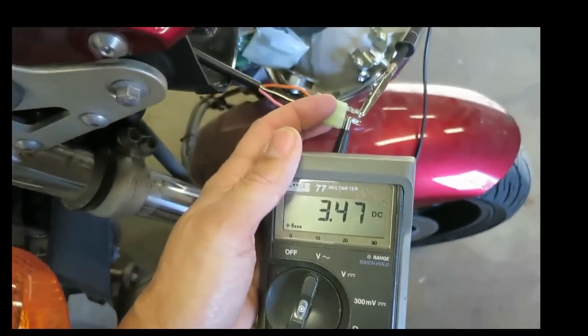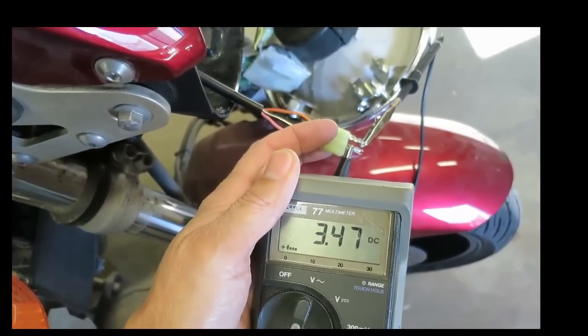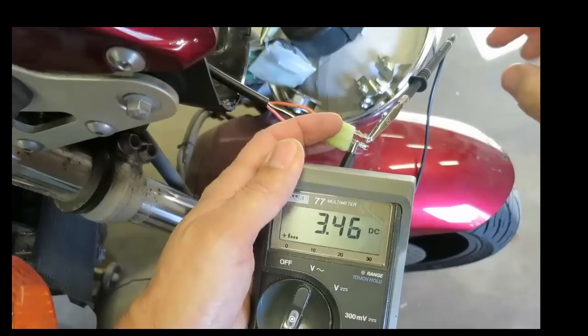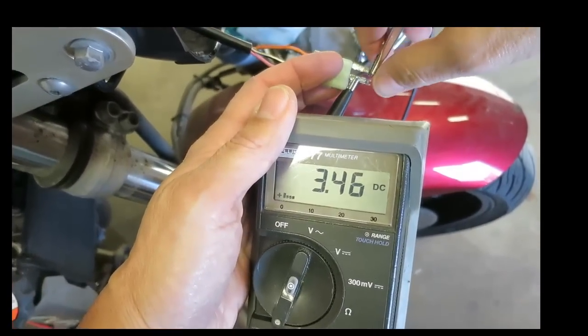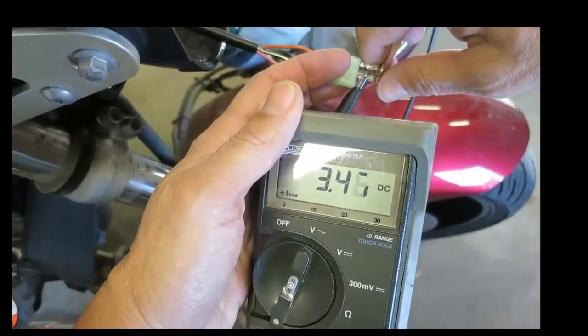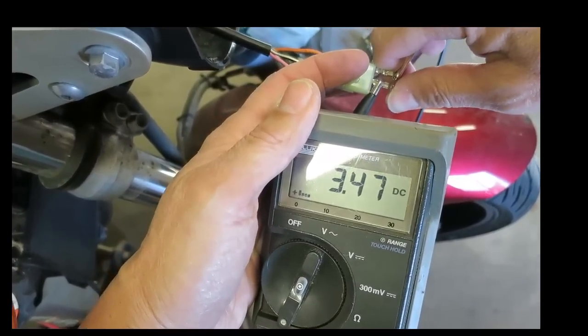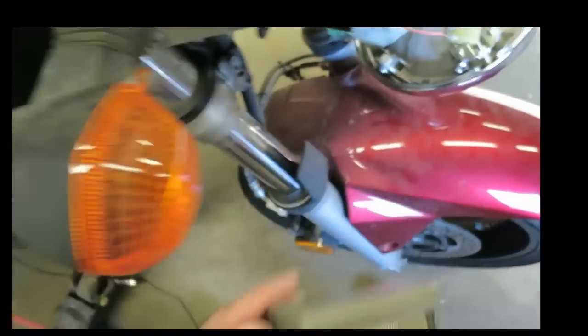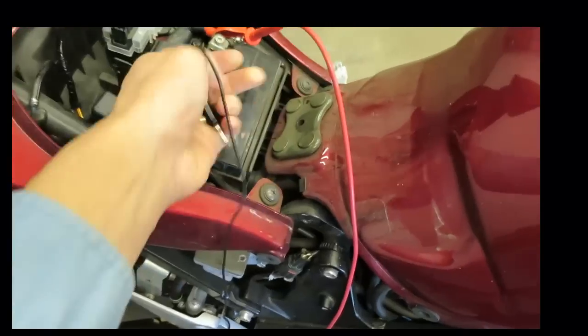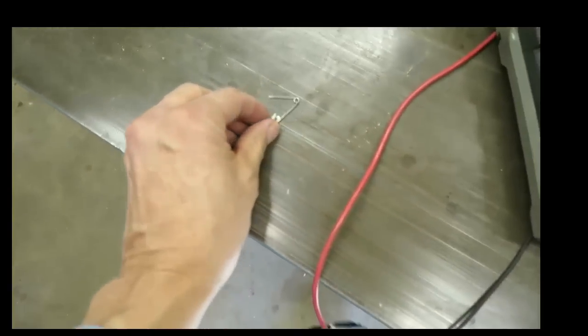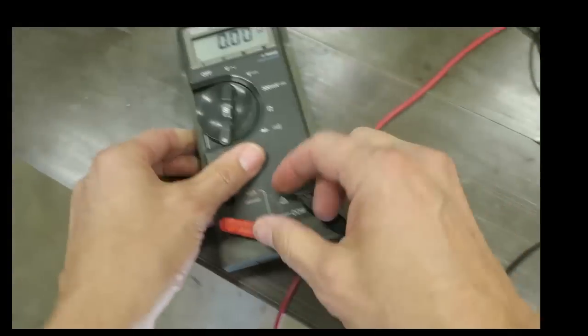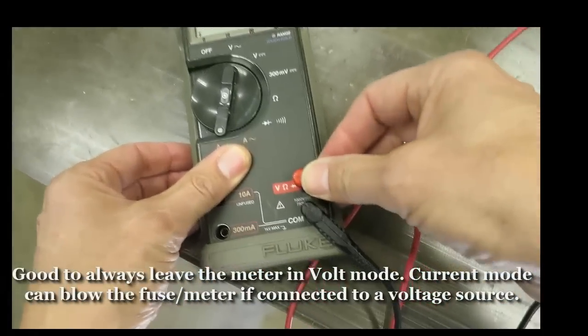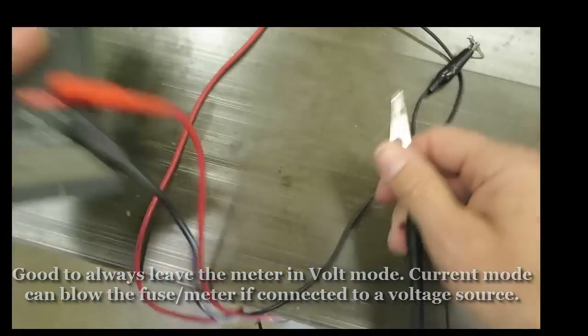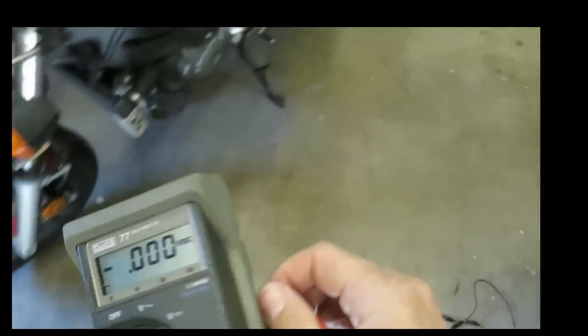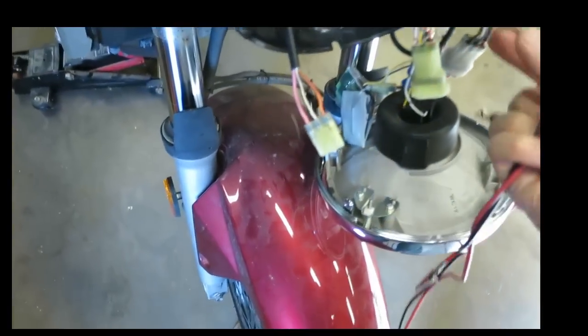So a healthy speed sensor, if you see no current draw, that would mean it's open. If you see a lot of current draw, that's a problem also. So 3 milliamps is probably ballpark healthy region for a SV650 sensor. Now the last thing we're going to do is measure. Let's unclip this. And use this push pin, safety pin, to put the multimeter back into voltage mode. Reconnect the speed sensor.